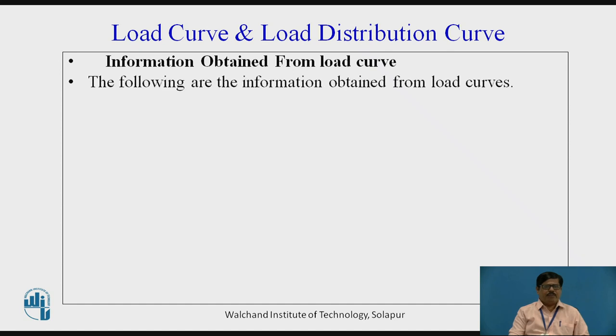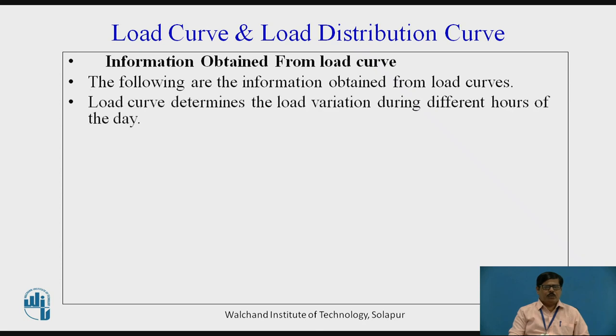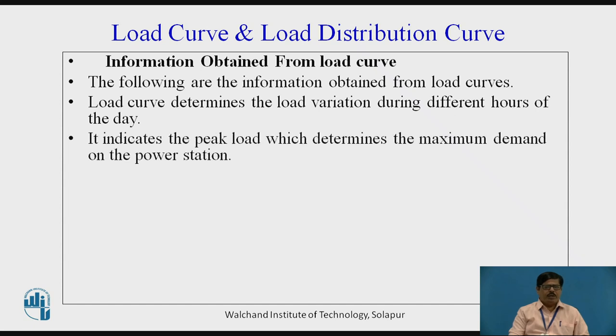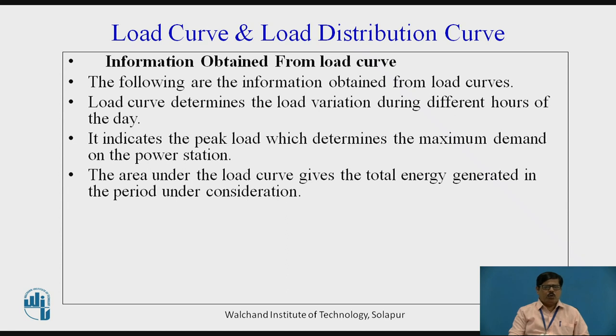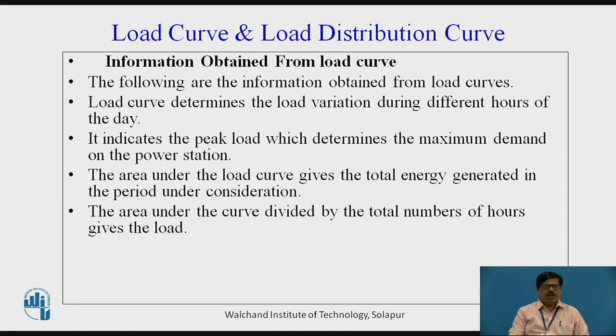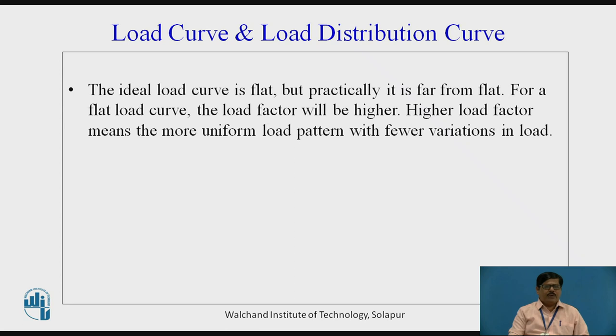Now, what information do we get from the Load Curve? The Load Curve determines the variation of load during the different hours of the day. It also indicates the peak load on the power station, which determines the maximum demand on the power station. The area under the Load Curve gives the total energy generated in the period under consideration. Also, the area under the Load Curve divided by the total number of hours gives the average load supplied by the power station. The ideal Load Curve is flat, but practically it is never flat — it will be fluctuating all the time. For a flat Load Curve, the load factor will be higher, so it is beneficial if the load on the power station remains constant, giving maximum load factor. Higher load factor means a more uniform load pattern with fewer variations in the load.